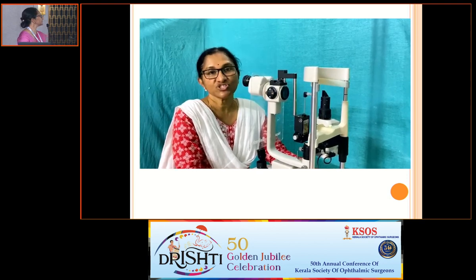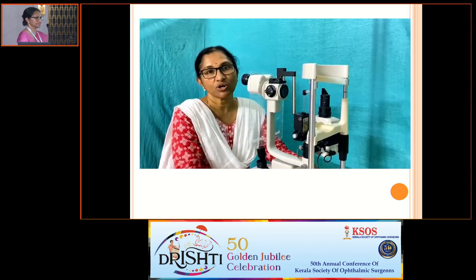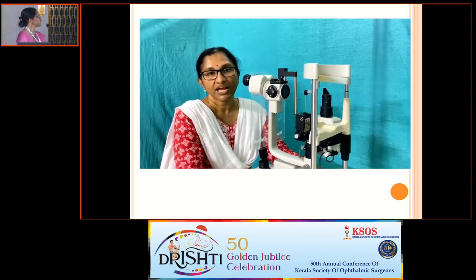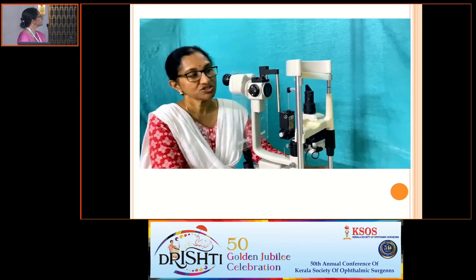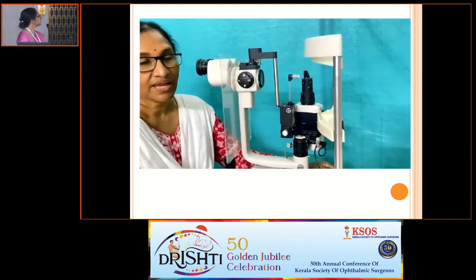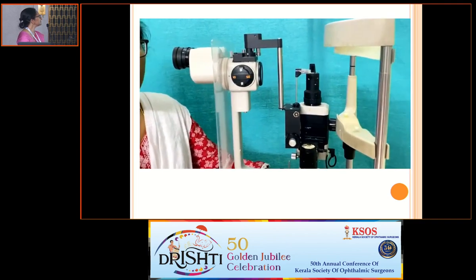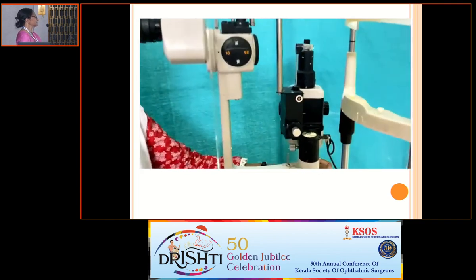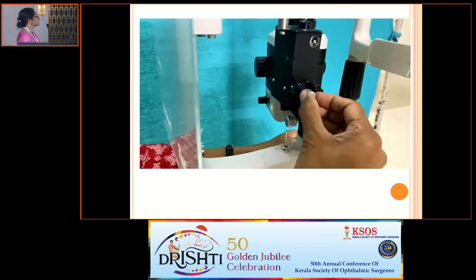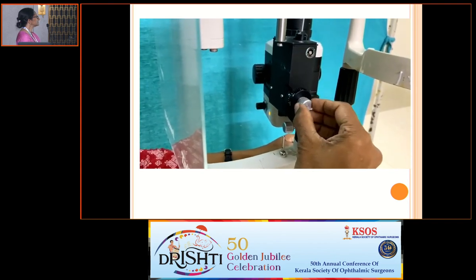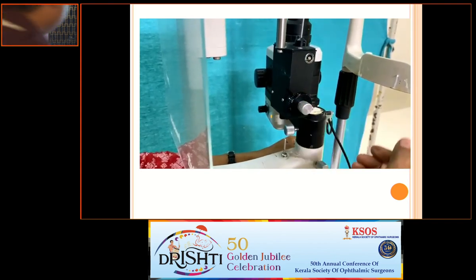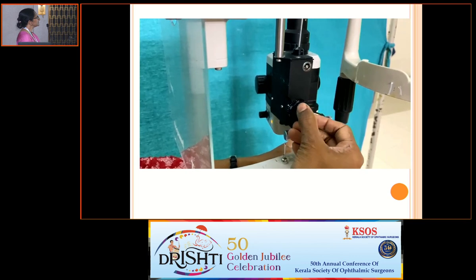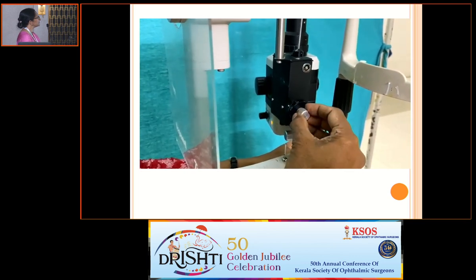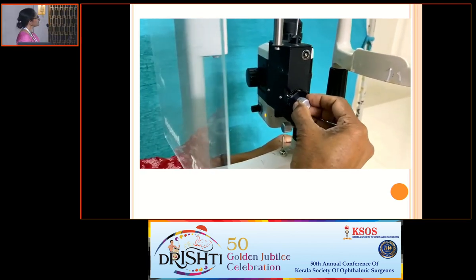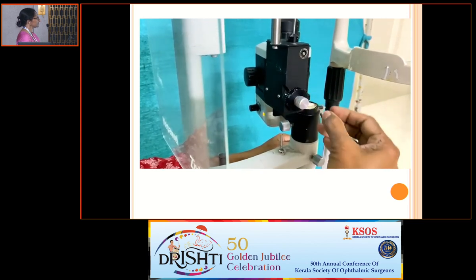Let us see how to check the calibration error for Goldmann Applanation tonometer. First of all, mount the Applanation tonometer on the slit lamp. The calibration error checking should be done at dial positions 0, 2 and 6. To check the calibration error at position 0, we have to rotate the knob to position 0.